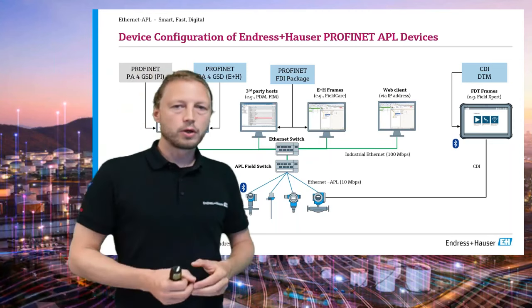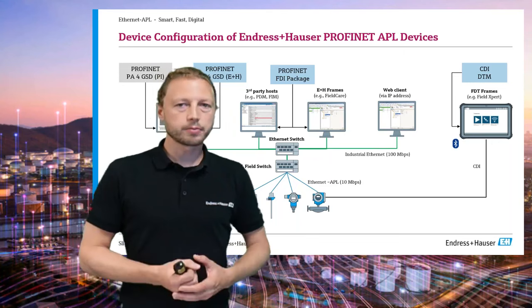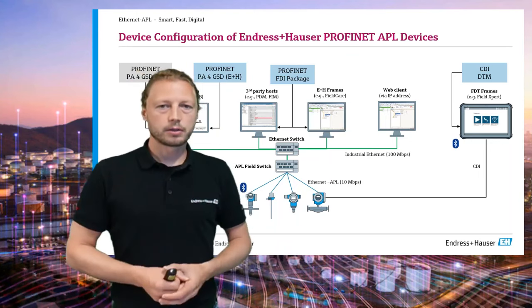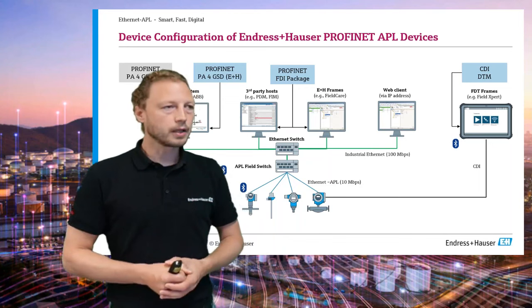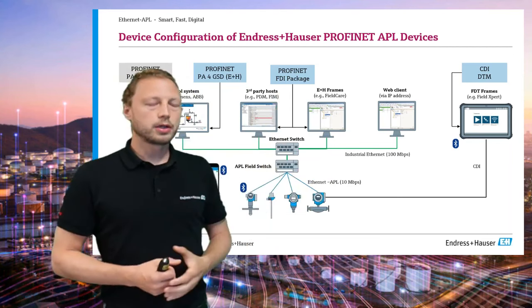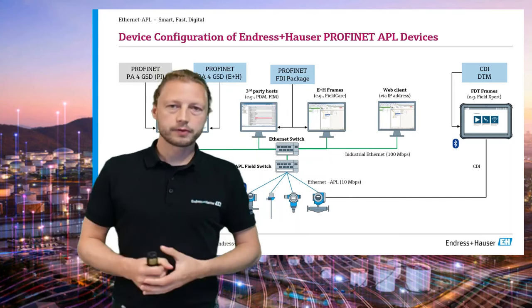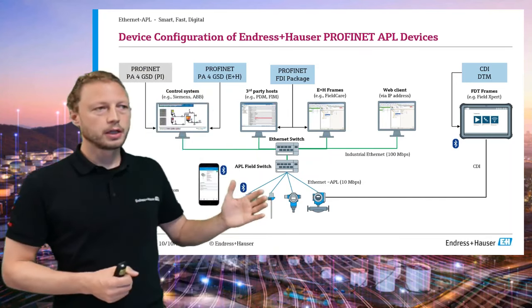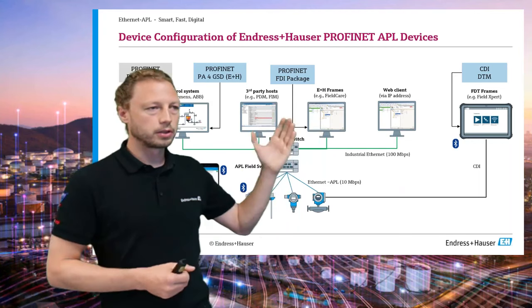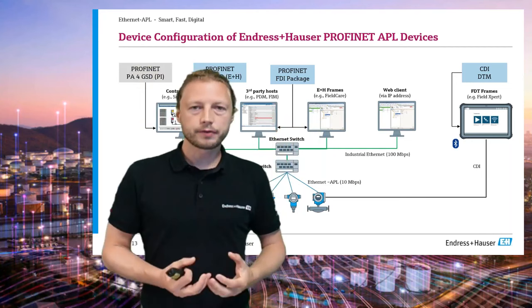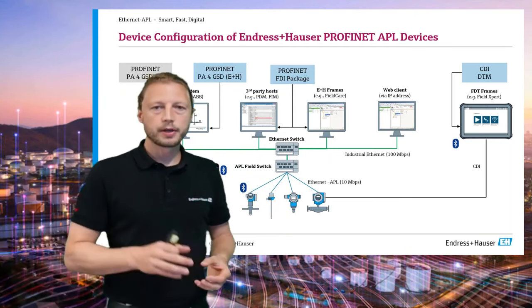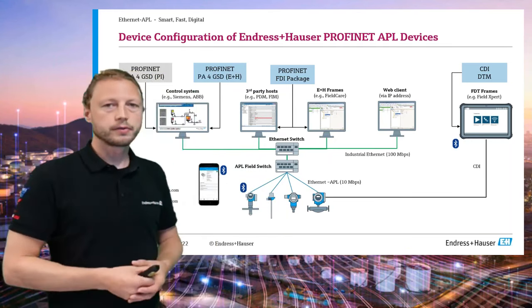For those using asset management software like FieldCare, Simatic PDM, ABB's FIM, Yokogawa's PRM, or Emerson's AMS — you want to keep and continue using these tools. In the future, all new instruments from us will come with FDI packages beginning of next year. The major advantage: independently of which control system or host configuration tool you use, a single FDI package can be implemented — one driver package that fits all different systems for device configuration.